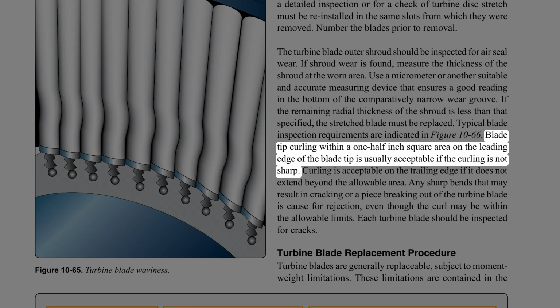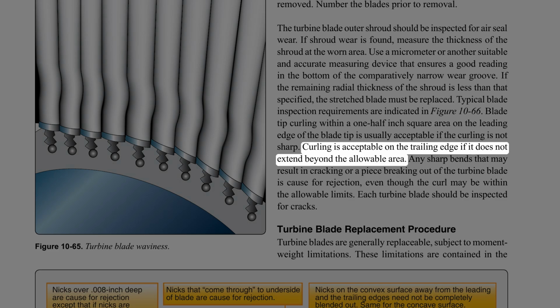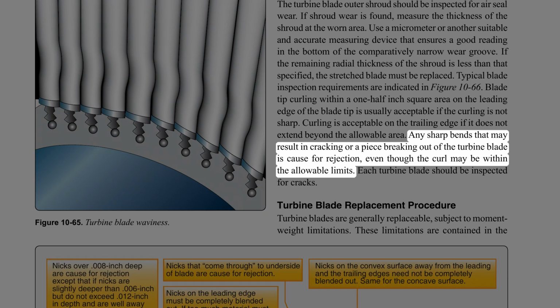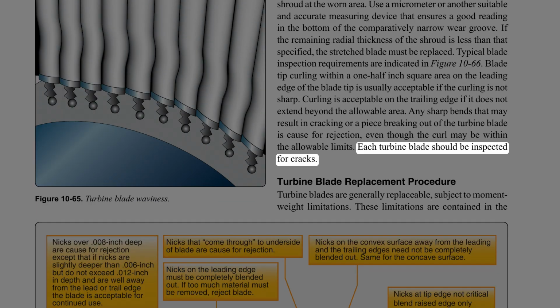Blade tip curling within a 1/2 inch square area on the leading edge of the blade tip is usually acceptable if the curling is not sharp. Curling is acceptable on the trailing edge if it does not extend beyond the allowable area. Any sharp bends that may result in cracking or a piece breaking out of the turbine blade is cause for rejection, even though the curl may be within the allowable limits. Each turbine blade should be inspected for cracks.